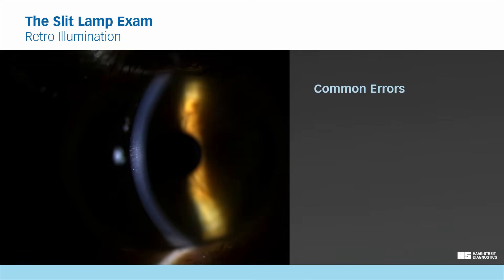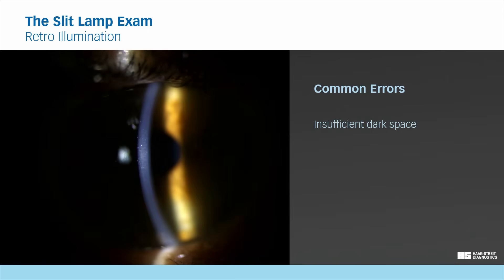When examining the cornea, make sure that you create sufficient distance between the direct slit beam and the area illuminated from behind by choosing a wide angle of illumination to microscope. Otherwise, when scanning the cornea, the direct illumination may obscure or wash out the views from the indirect retroillumination.